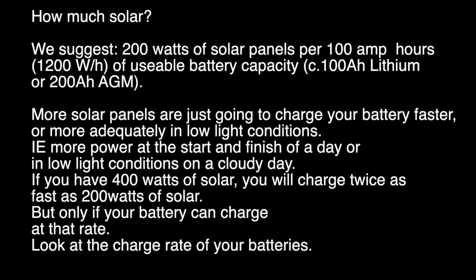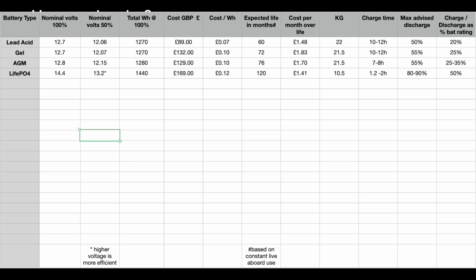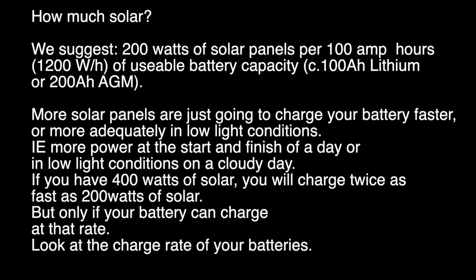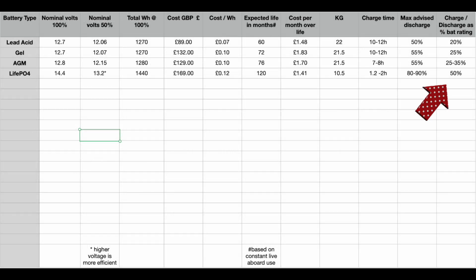Look at the charge rates for your batteries, we've put them in that table. This is where lithium has a distinct advantage over lead-acid batteries: typically, lithium batteries can charge at about 50% of their overall capacity. To simplify, a 100 amp hour battery can charge at 50 amps, and a 200 amp hour battery bank can charge at 100 amps. You simply can't do that with lead-acid based batteries.